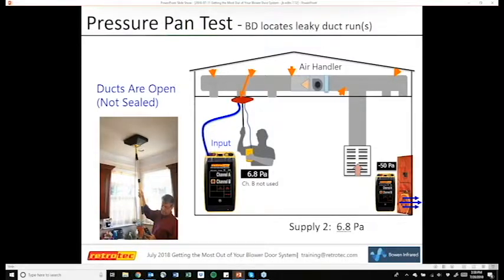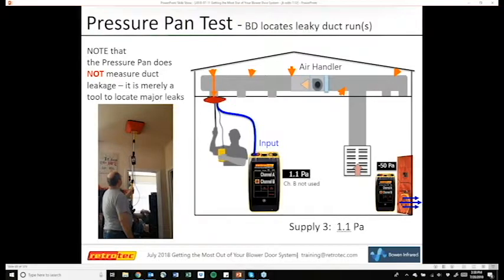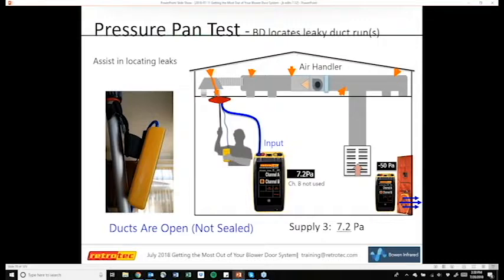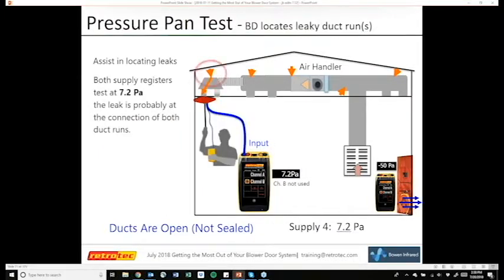And as I was saying about different branches, this is what I wanted to show. If you have two different branches coming off of one connection here, say you test this supply and you get 7.2 Pascal, and you test this one off the same connection and you also get 7.2 Pascal, then your leak is probably coming from this connection since these two are reading the same or similar. That's a way you can pinpoint where it's coming from instead of running your duct tester and then going around aimlessly trying to check all connections. This is a way you can make it faster.